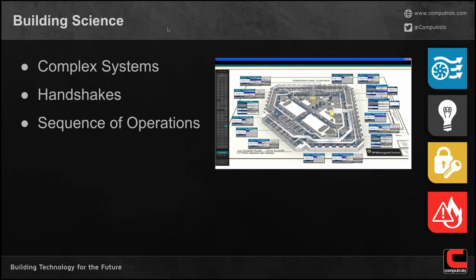One of the energy efficiency strategies we use in the building automation industry is a feature called optimal start stop. Say you have a space within a building that's going to be occupied at 8 a.m. every morning, Monday through Friday. An optimal start stop program lets you enter the desired set point of that space at a given time each day. The system then runs computer algorithms to determine the very last second it can start the cooling equipment in order to achieve that set point when the space will be occupied. As a result, there are energy savings.